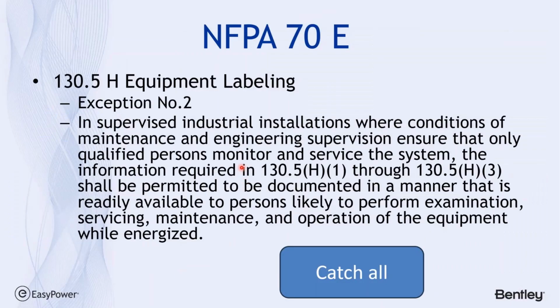And I understand the catch-all, and I don't label that in a negative term, but Article 130.5(H), in discussing equipment labeling, says in a supervised industrial installation where conditions of maintenance and engineering supervision ensure that only qualified persons monitor and service the equipment, the information required in 130.5(H)(1) through (H)(3) shall be permitted to be documented in a manner that's readily available to persons likely to perform examination, servicing, maintenance, and operations of the equipment while energized. So again, this is a consensus standard, and that means I can read into it what I feel is the situation for my organization. And this document says I can put whatever I want on the label and in the documentation that personnel use for maintenance.